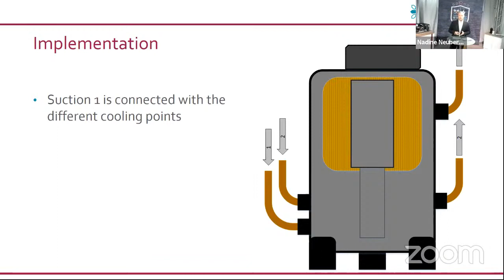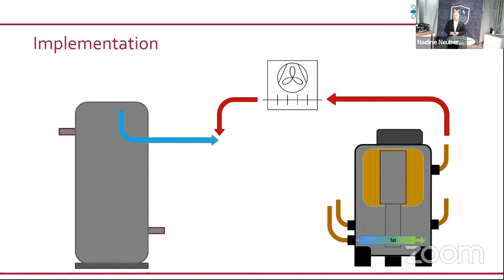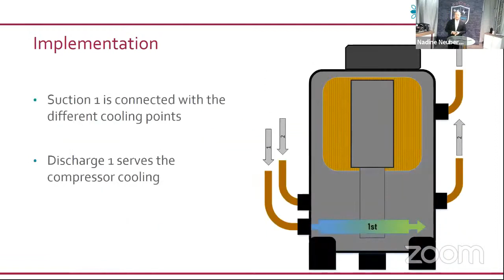This suction gas is compressed in the first stage, and the discharged gas doesn't go out directly. It serves the compressor cooling inside of the shell. After the compressor cooling inside of the shell, the compressed gas streams out of the discharge 1 line. This discharge 1 gas streams through a desuperheater, and there we cool the desuperheated gas. At the outlet of the desuperheater, we create a mixture out of flash gas and desuperheated discharge gas, and this mixture is inserted in the suction 2 line.